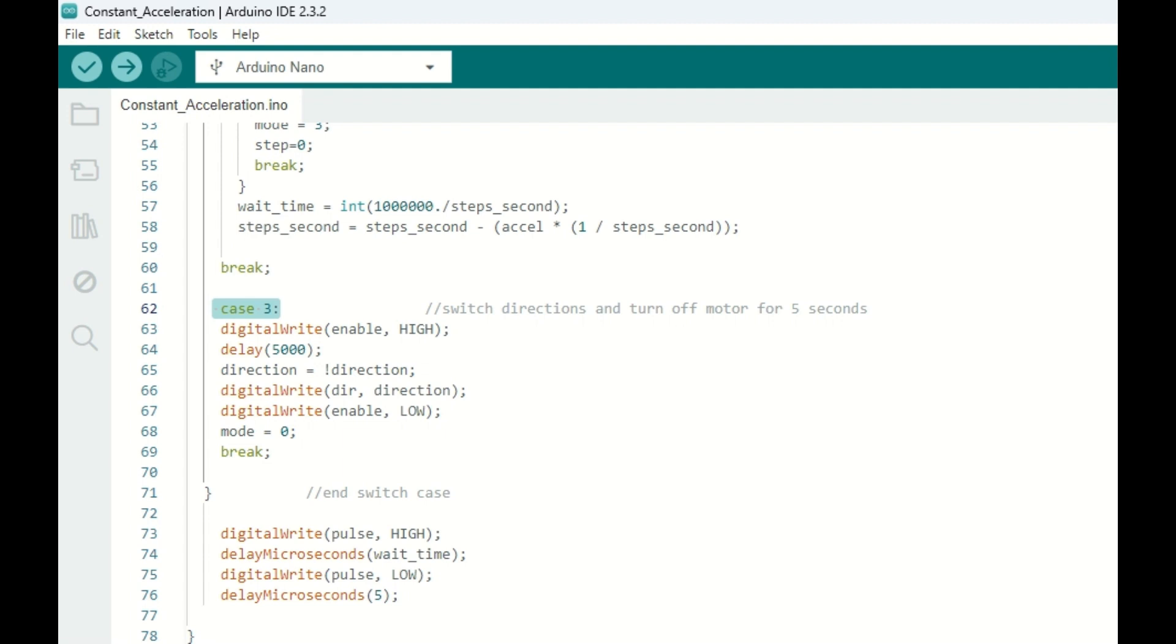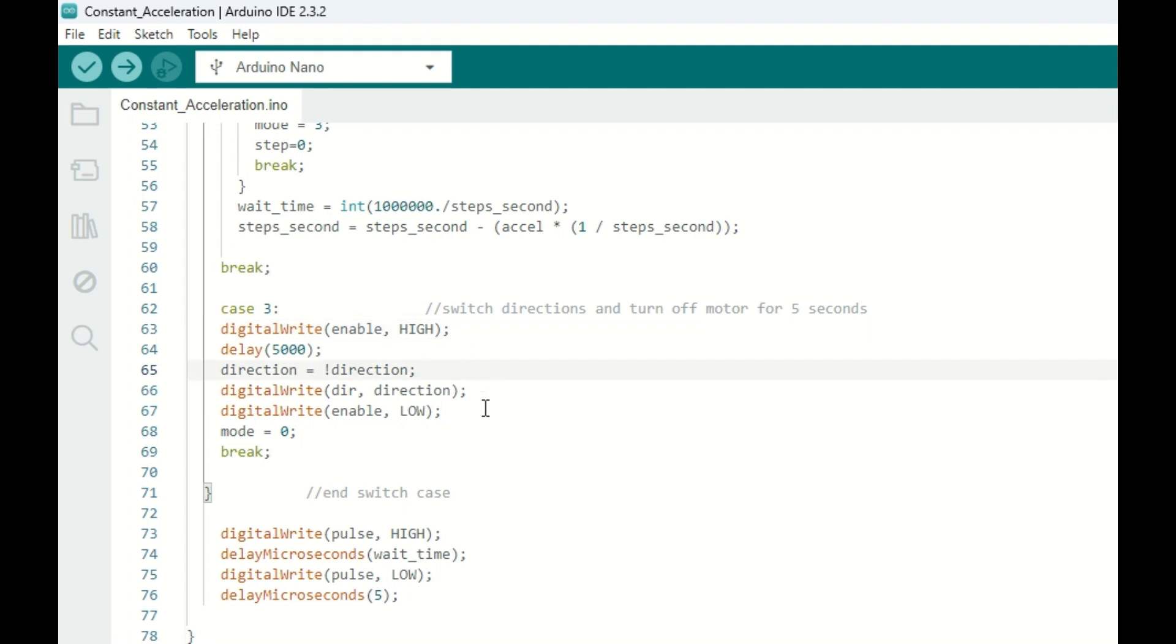Now after we've decelerated back to the minimum speed, we move on to case 3. Case 3 actually turns off the motor with this enable high command. We wait five seconds, and then switch direction of the motor and re-enable the motor. Then we go back to case 0, which starts the process all over again, going the opposite direction.